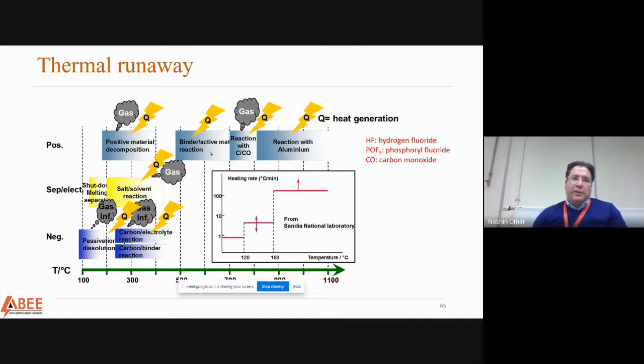Problems start when you go outside the normal operating conditions of a battery. Consider going over 70 degrees: the electrolyte becomes unstable, starts creating gases, and chain reactions start slowly. That's what you see here — that's typically the process of thermal runaway.